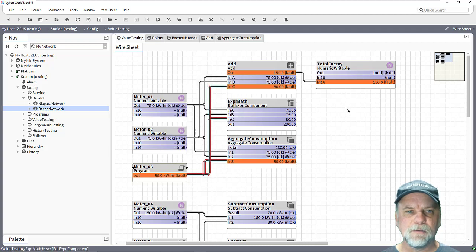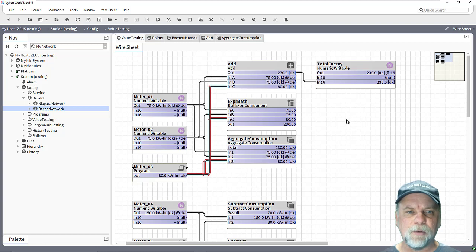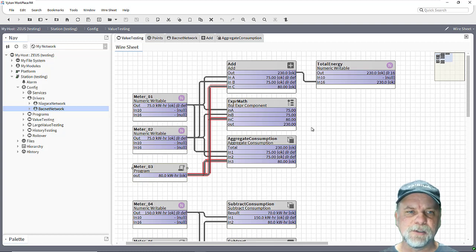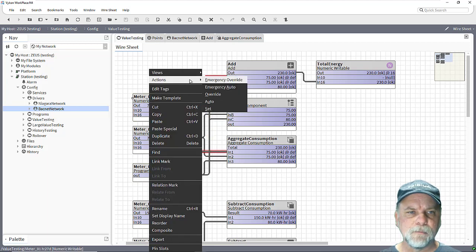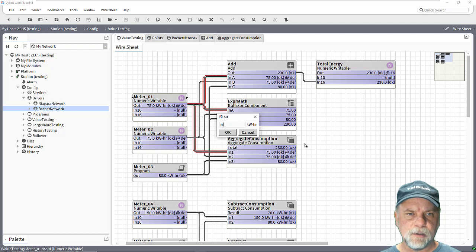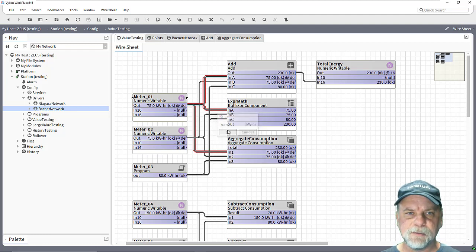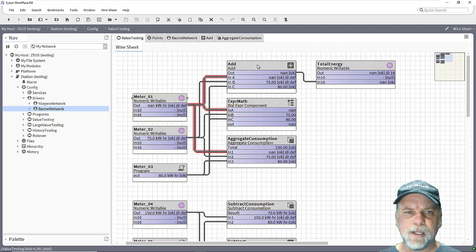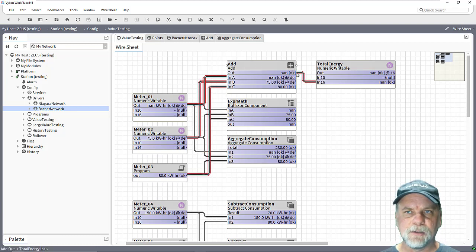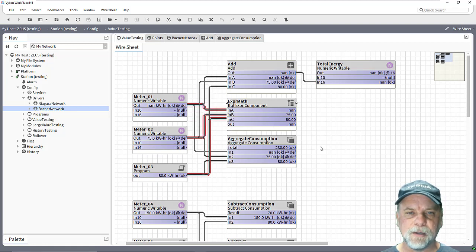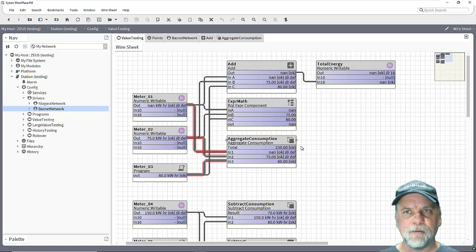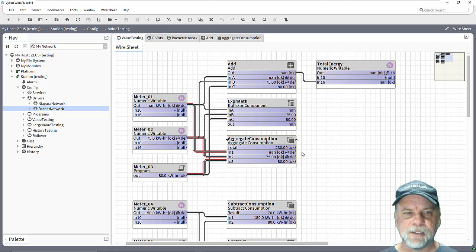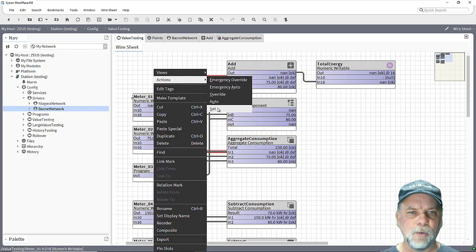So let me clear the fault now. Some other things could be invalid values as well which could impact your control logic and or your history collection. So let's say for example that I set this value to NaN on this meter one simulation point. You'll see the add block sees that NaN value on the input which ultimately results in NaN value on the output and the same thing happens with the expression block, but the aggregate consumption block in this case ignores that invalid value input of NaN and just uses the last known value so again we maintain a better total there.